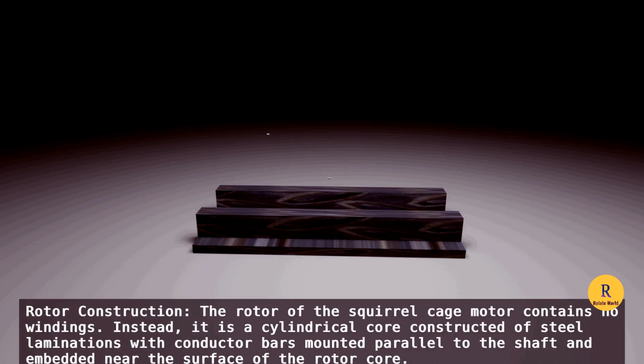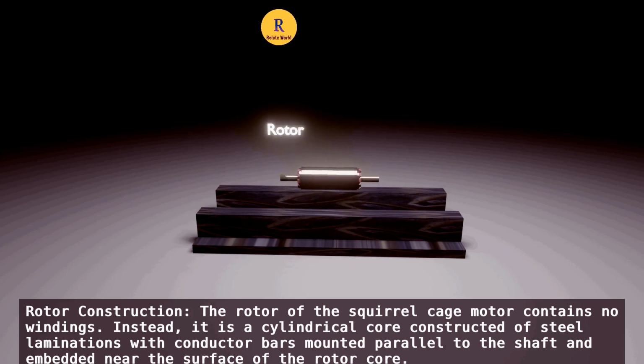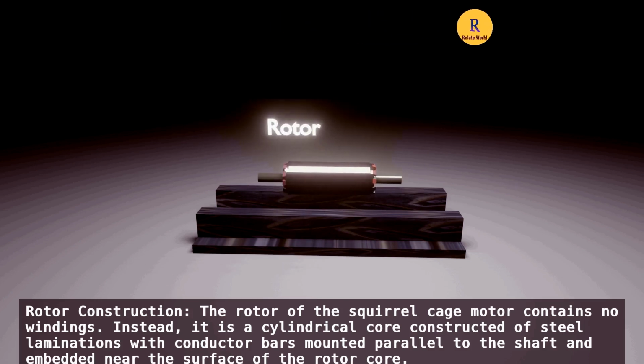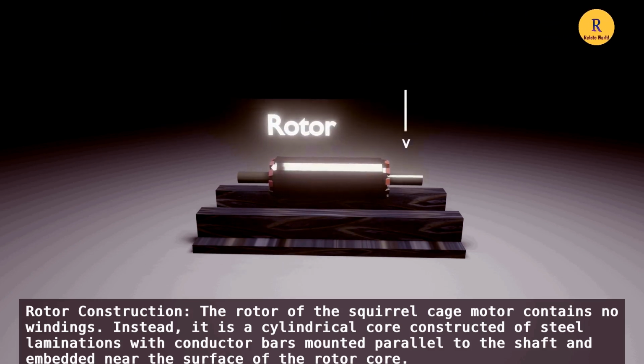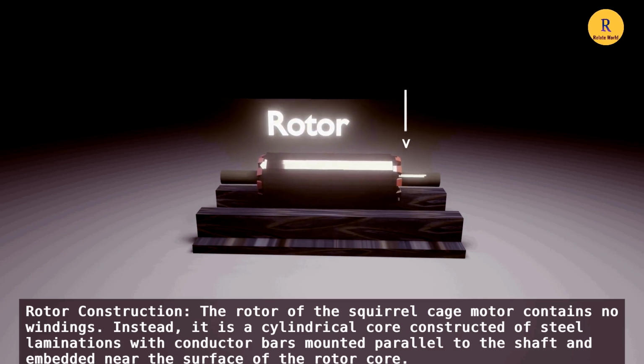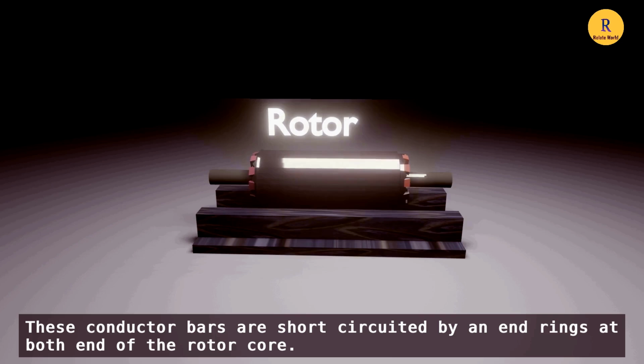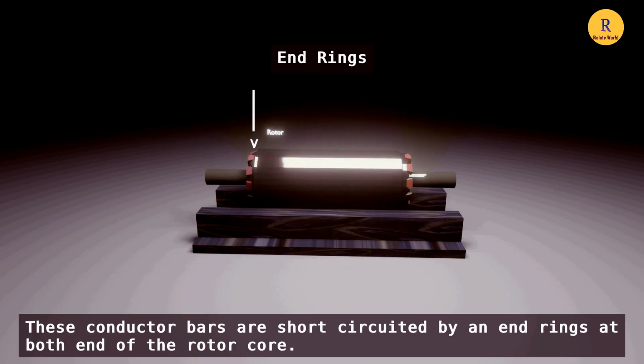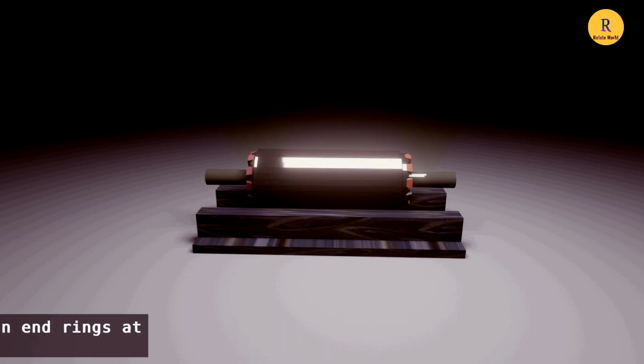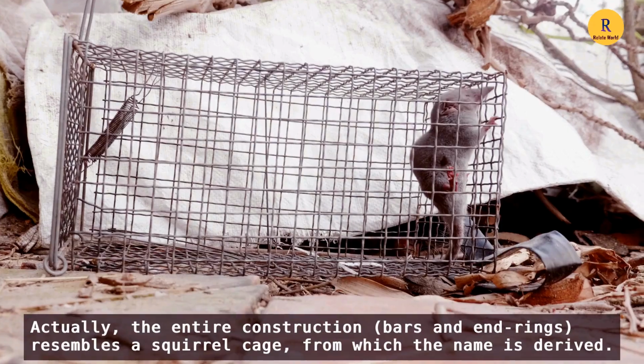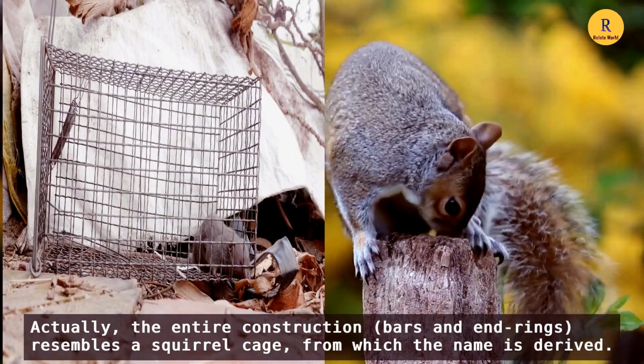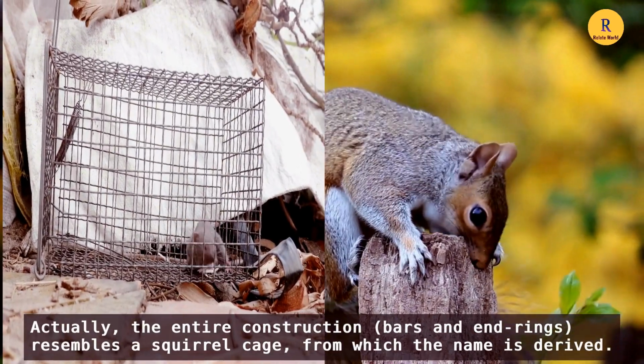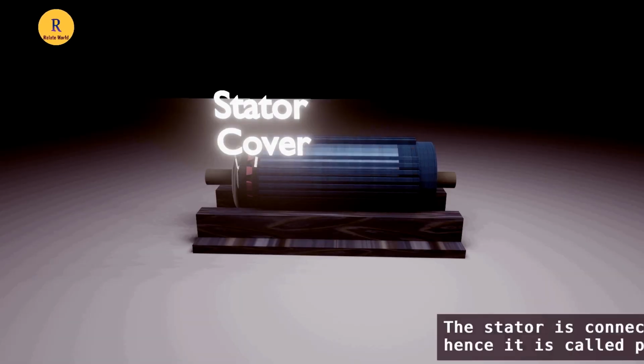Rotor construction. There are no windings in the rotor of the squirrel cage motor. Instead, it is a cylindrical core constructed of steel laminations with conductor bars mounted parallel to the shaft and embedded near the surface of the rotor core. These conductor bars are short-circuited by end rings at both ends of the rotor core. Actually, the entire construction, bars and end rings, resembles a squirrel cage, from which the name is derived.